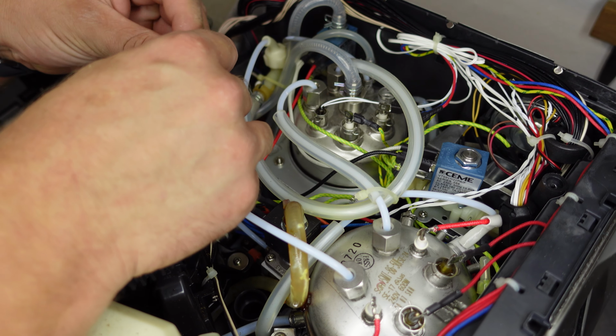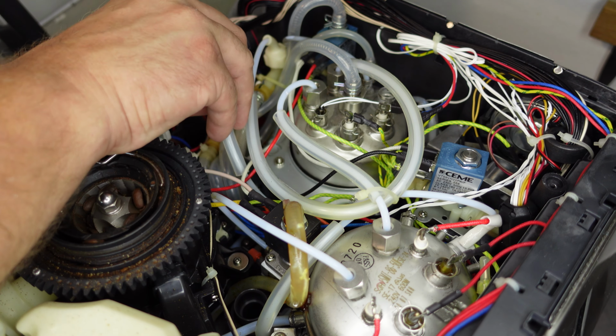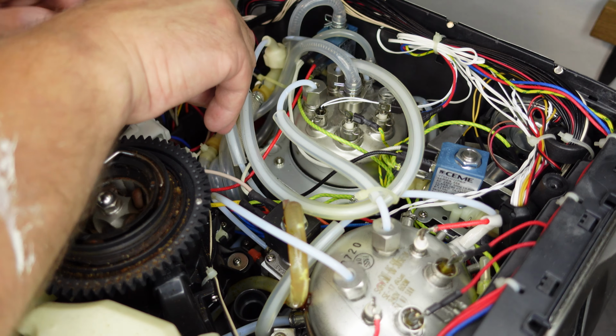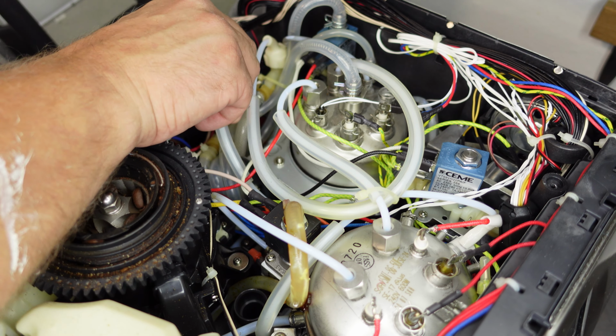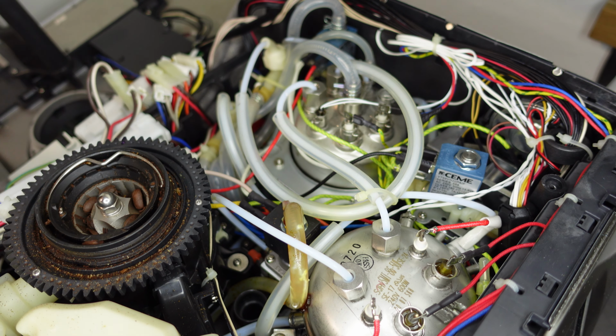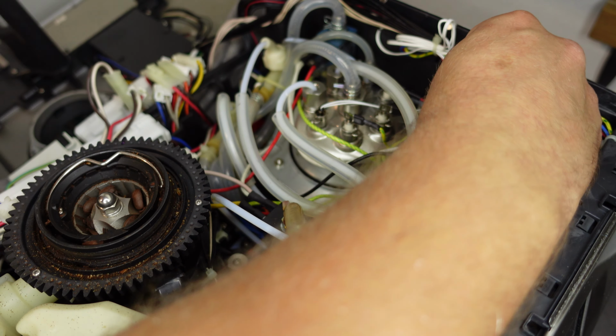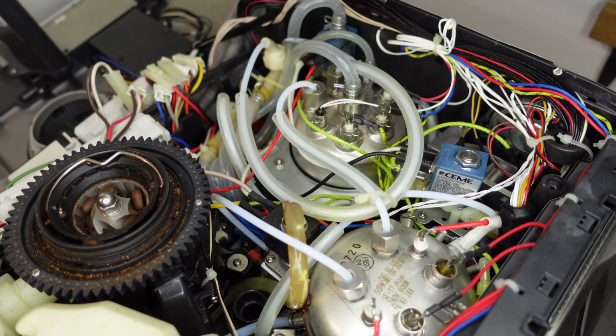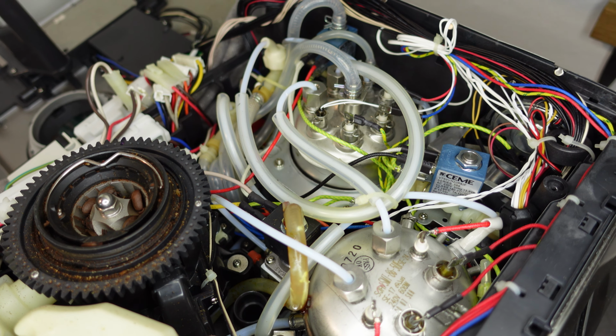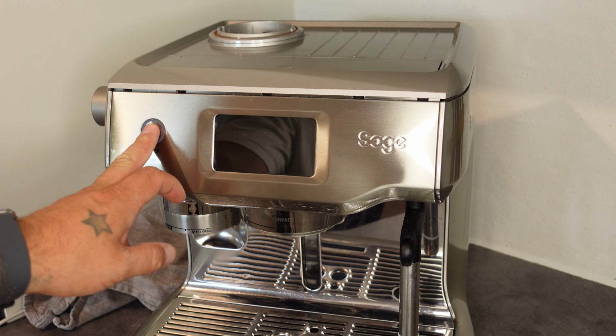Now the hose needs to be reattached to the pump. Again, it's important to replace the O-ring to avoid leaks. The last step before testing the machine is reinstalling the probes. If you reuse the old probes, make sure to fit new O-rings, but I recommend replacing them with brand new ones. Now for the fun part, let's test if it works.